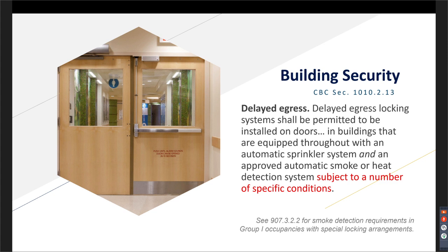But Gary can talk a little bit more about the delayed egress. Yeah, rather than going into the specifics, one of the criteria here is that delayed egress is only allowed in fully sprinklered buildings. And you see the word "and" is italicized. That's a state amendment that says sprinklers and an automatic smoke detection system. So the note below, 907.3.2.2, for all the requirements for smoke detectors in these special locking arrangements. So that can be pretty big. So if you've got an area that has delayed egress, the smoke detection throughout all these spaces, that's a lot of spaces where there'll be additional smoke detection that's needed. And again, the entire building has to be sprinklered in order to have this.